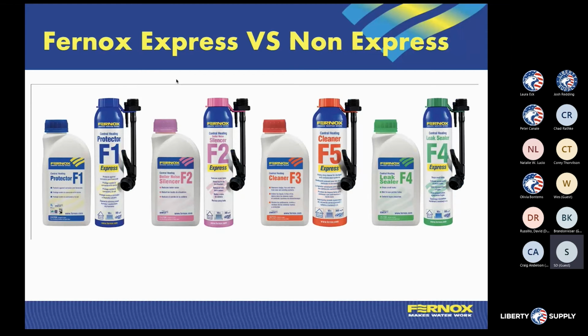So in the smaller versions, we have product that is in both a liquid format, which is that pint bottle to the left, and that skinnier looking bottle is a pressurized canister. So what that means is on a 12-pound standard hydronic system, I can walk up to that particular system, find an access point like a boiler drain, and put that system into place. And because it's pre-pressurized, it can overcome the pressure of the 12 pounds. So I'm not draining the system back to add my inhibitor in.